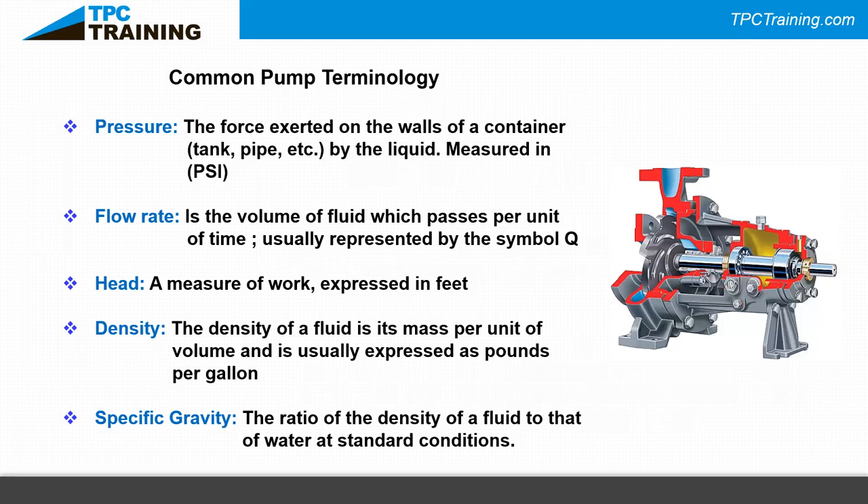Head is a measure of pressure expressed in feet, based on the calculation that at standard atmosphere a cubic foot of water — 12 by 12 by 12 — weighs approximately 62.3 pounds. There are 144 cubic inches in a cubic foot. Dividing 62.3 by 144 gives 0.432 pounds. To make one pound of pressure you stack two of those one-inch-square columns of water 12 inches tall and add 0.31 of another — that's why pumps are described as head devices.